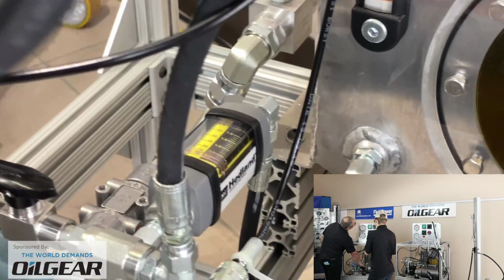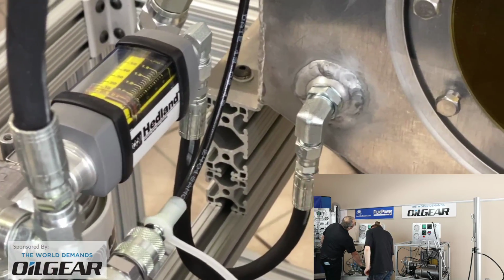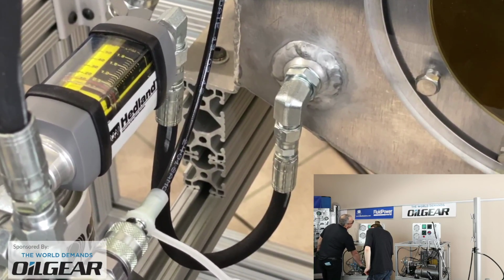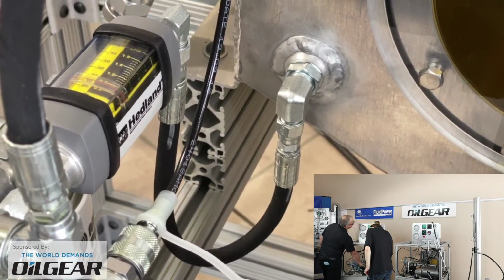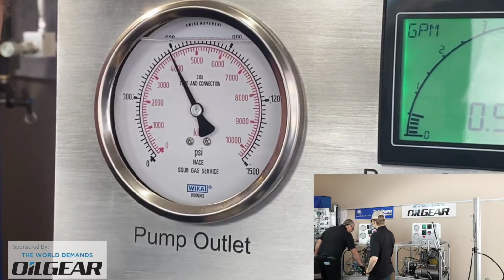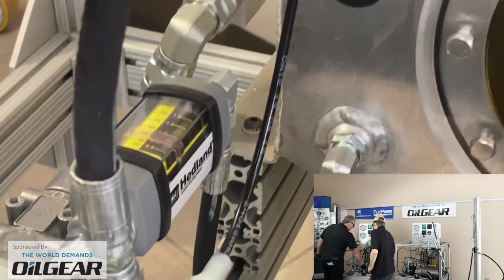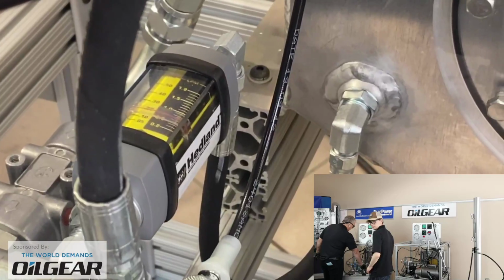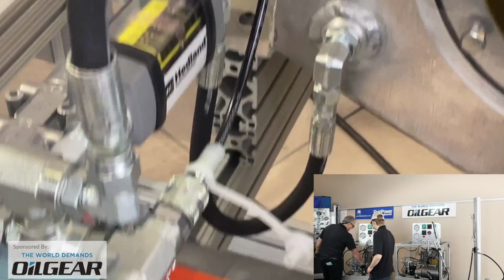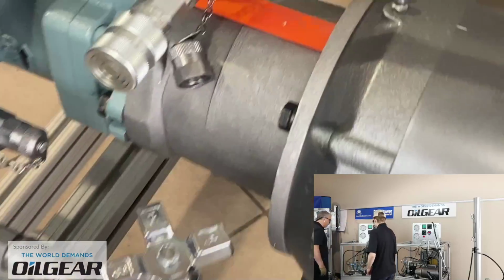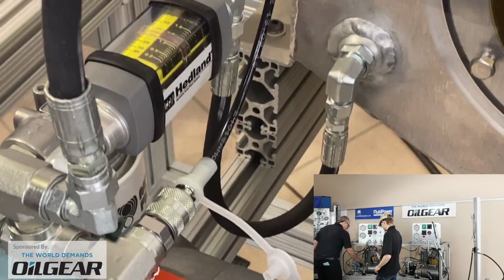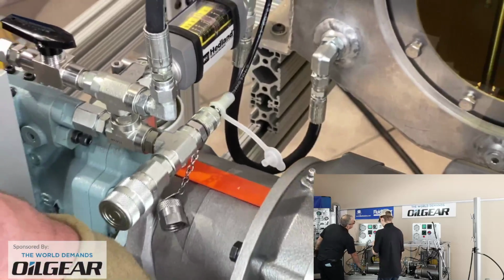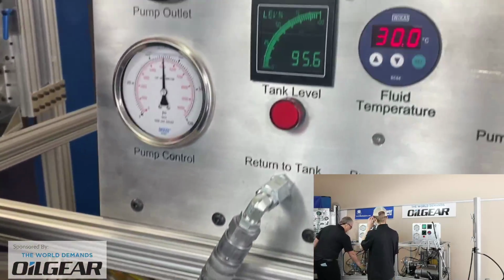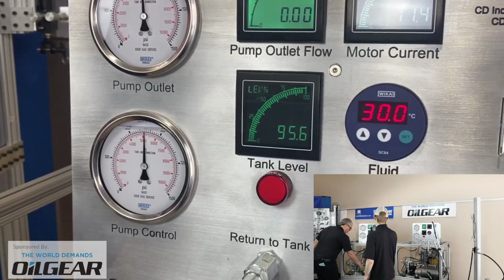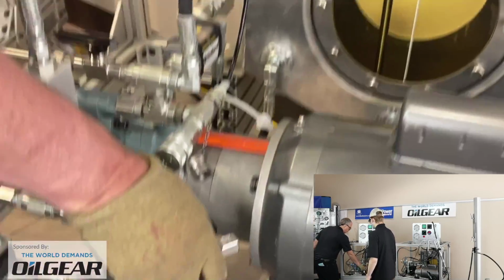We're nowhere near 750, our pressure compensate pressure. We're only at about 450 pump outlet pressure. Now 500 pump outlet pressure, 550, 600 psi, and we're up to 0.15 GPM of flow on the case drain. And if I shut in the pump's outlet you'll see that there is the highest level of flow on that case drain line that you'll ever see, due to the pressure, due to the clearance between parts, and also due to controller exhaust and the maximum stroke of the control piston.